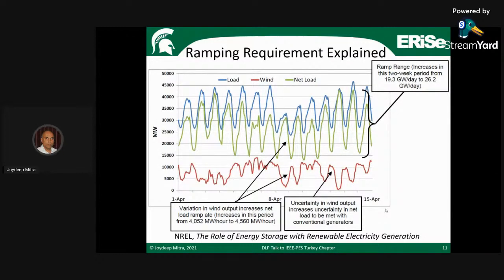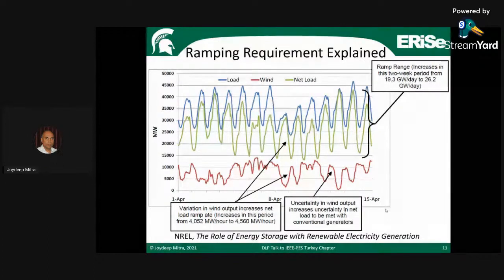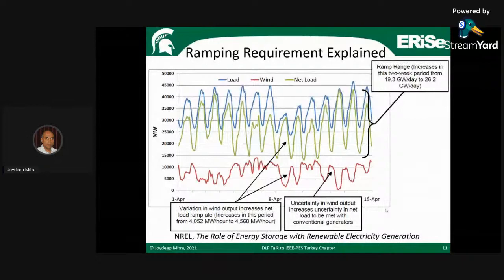You'll see two other things from this green curve: the range, that is the difference between the peak and the trough, has also increased compared to the blue curve, which means the conventional generators will have to ramp up and down a lot more. That is the ramp range. And if the ramp range increases for the same period of time, the ramp rate will also have to increase. Realize that not all generators are able to ramp up this quickly. Some are, and so generators with ramping capability are in high demand. This gives you an idea of ramping requirements.